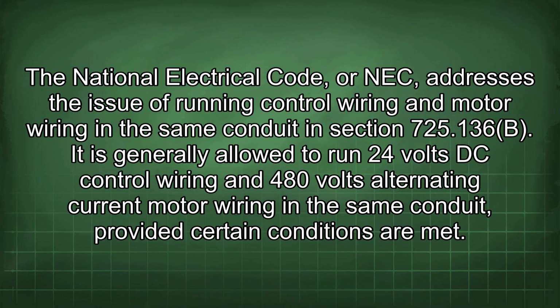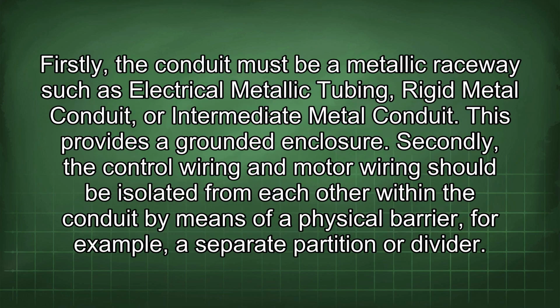The National Electrical Code, or NEC, addresses the issue of running control wiring and motor wiring in the same conduit in section 725.136(B). It is generally allowed to run 24 volts DC control wiring and 480 volts alternating current motor wiring in the same conduit, provided certain conditions are met. Firstly, the conduit must be a metallic raceway such as electrical metallic tubing, rigid metal conduit, or intermediate metal conduit. This provides a grounded enclosure.